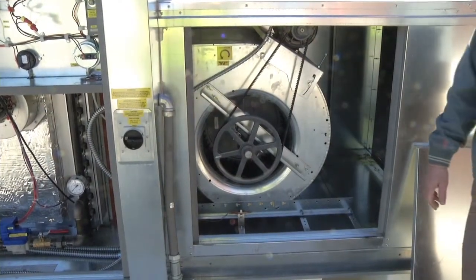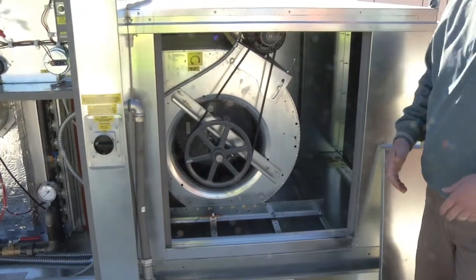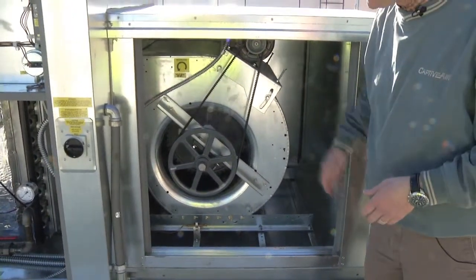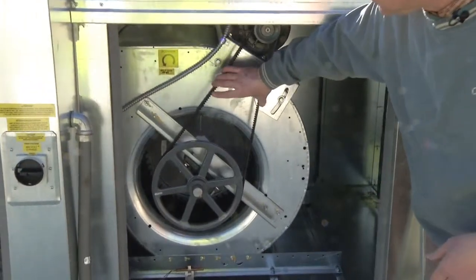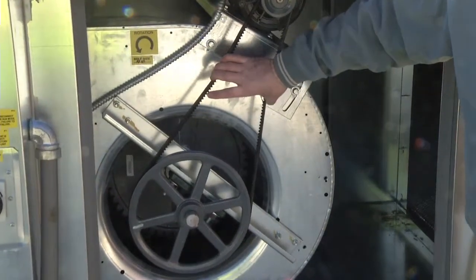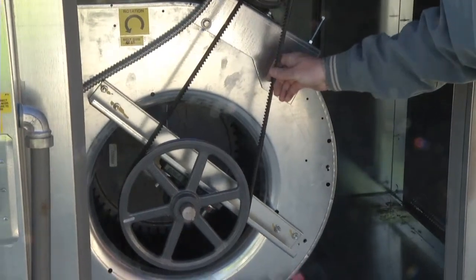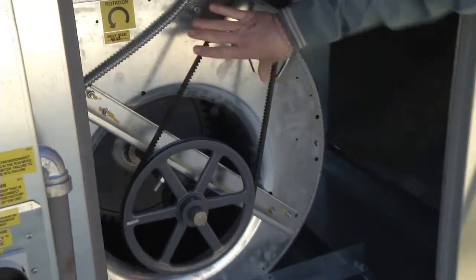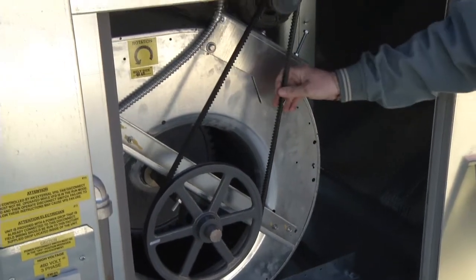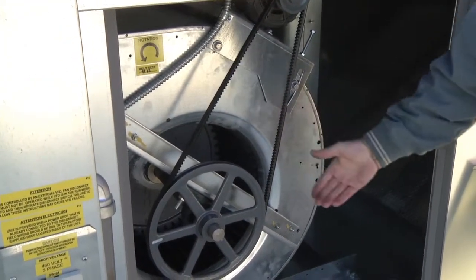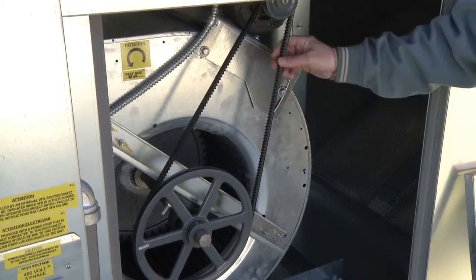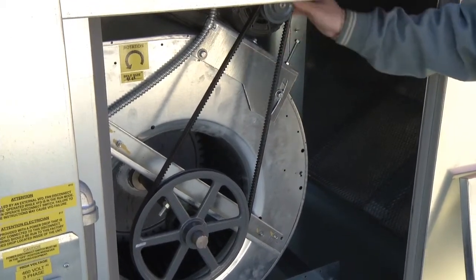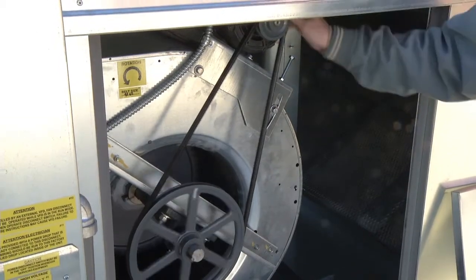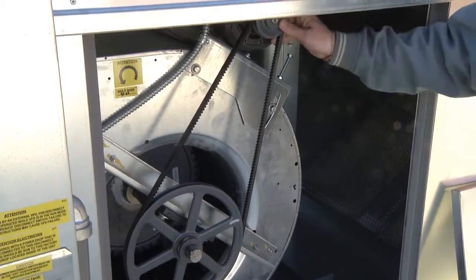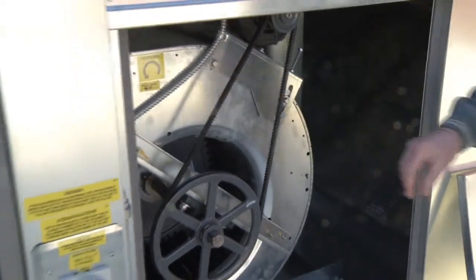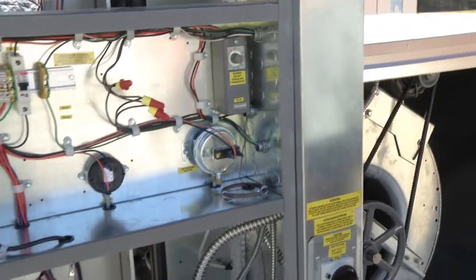Okay, besides the filtration, the only real basic part of maintenance for these units is to come up again twice to three times a year, and you're going to check your belt tension. You should have between a half to three-quarter inch of play on the belt on both sides. This belt has excellent tension as it is. You're going to look for any type of rubber shavings at the base of the unit. What you're looking for is uneven wear in your belt. That could indicate there was an issue with the pulleys not being properly aligned, but as is, everything looks outstanding.